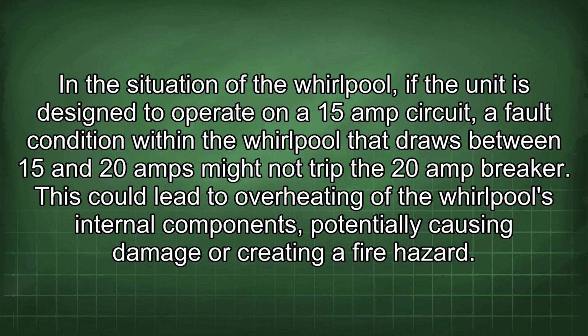In the situation of the Whirlpool, if the unit is designed to operate on a 15 amp circuit, a fault condition within the Whirlpool that draws between 15 and 20 amps might not trip the 20 amp breaker. This could lead to overheating of the Whirlpool's internal components, potentially causing damage or creating a fire hazard.